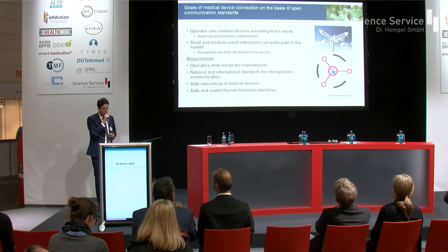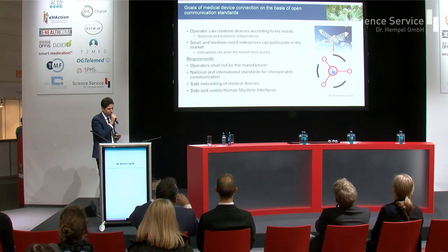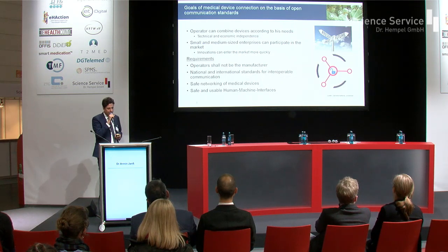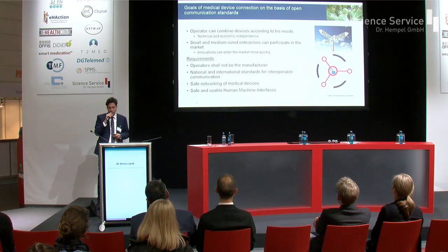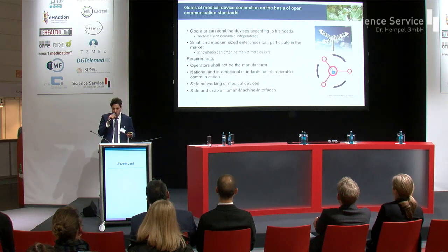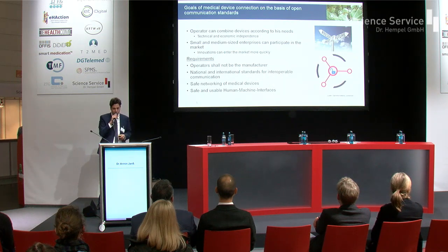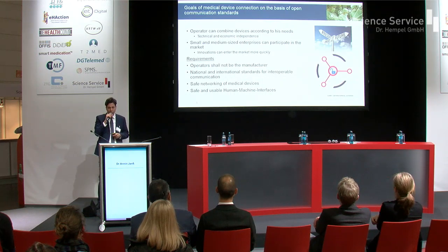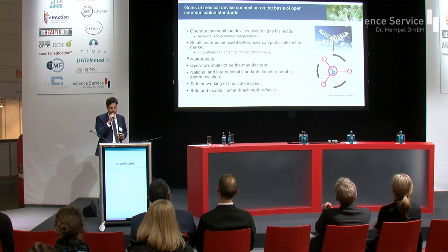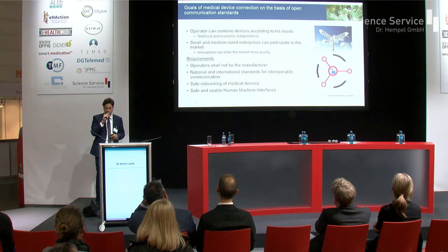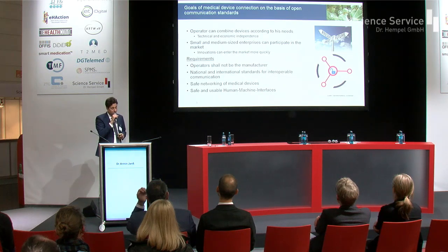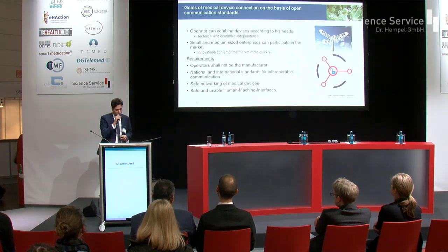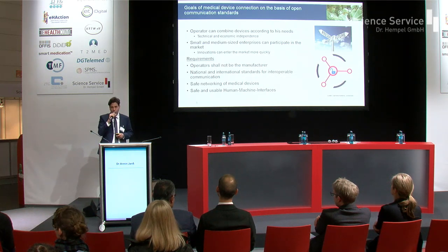put a base for these clinical operators in order to use this open interconnection of medical devices: the OR.NET standard. For clinical operators, it's clear they want to have flexibility, they want to be independent regarding the technology and also economical questions or requirements. And on the other side, small and medium-sized enterprises would now be able to participate in this market, which is now really difficult with the big vendors. But what we have to provide first, which kind of requirements we have to achieve: the operators shall not be the manufacturer.